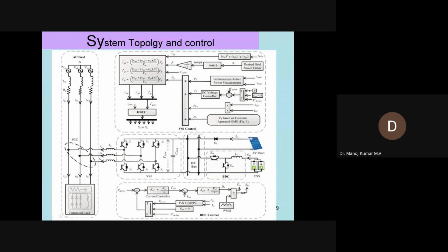There is one more power called P, P capital L and P small l. P capital L represents the power requirement by the load, and P small l represents the power used to maintain the DC link voltage, the DC bus voltage here. So this power is also required, and these are done in some other type of computation, some other type of control algorithm also.